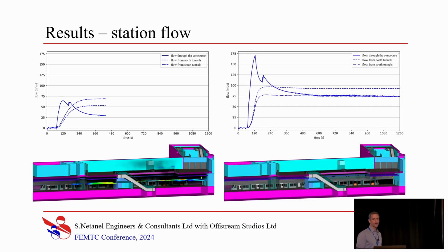So I added a few fans, a lot more air, no smoke coming up, that's good. And I would like to take a minute to talk about the flow as it is represented with these graphs. So first of all, between the initial and the final simulations, you can see that the basic behavior of the flow did not change. The amount of air obviously did, but what happens is fans start extracting in about 60 seconds.